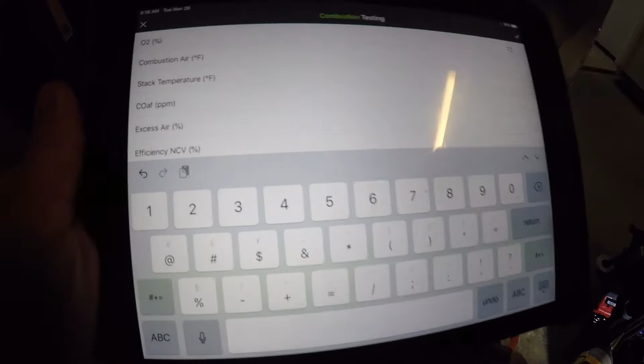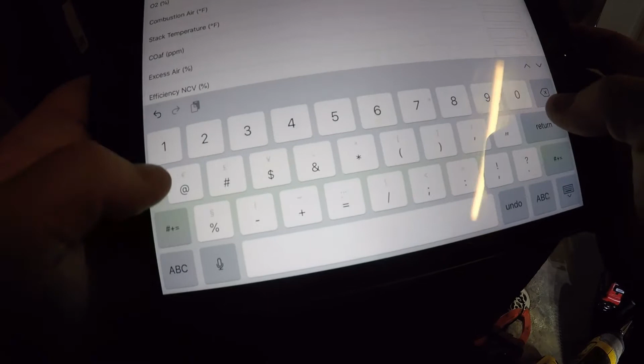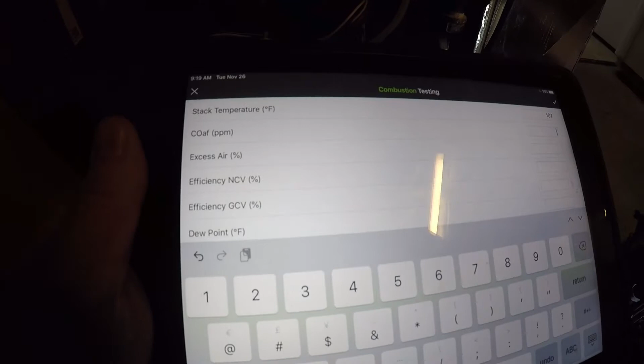My O2 is 7.2. My stack is 107. Excess air is 52. Oops. 107. Combustion air is 37. CO air free, I have to do a calculation because my meter doesn't do it, but we'll do that after. My O2 currently is 7.8. 37 degrees outside.